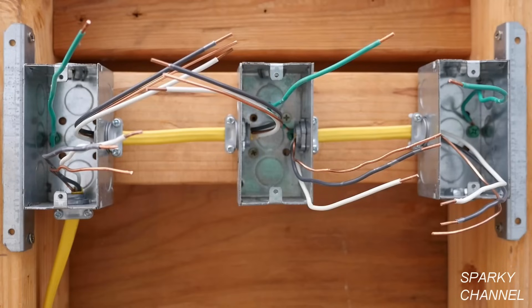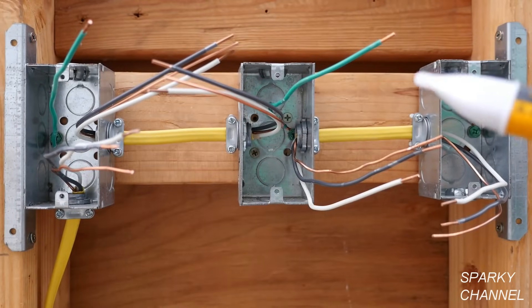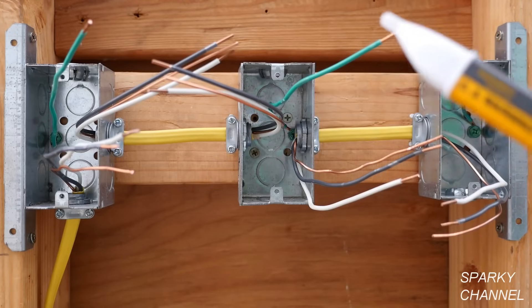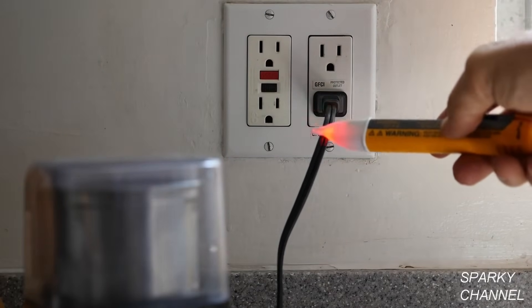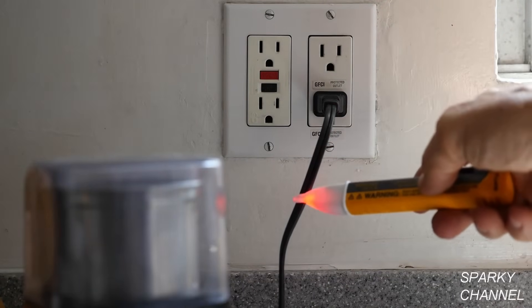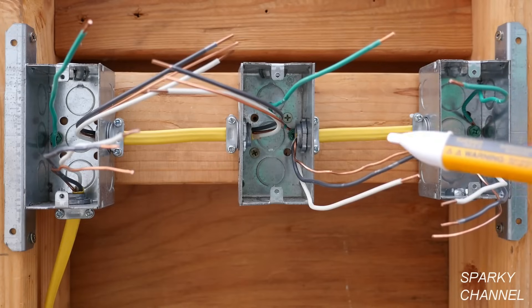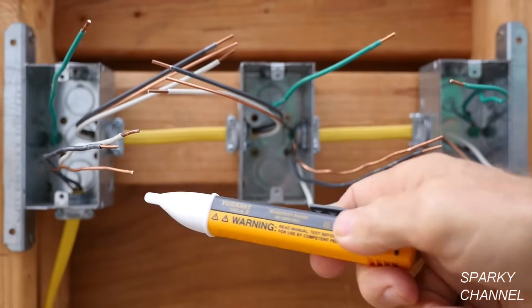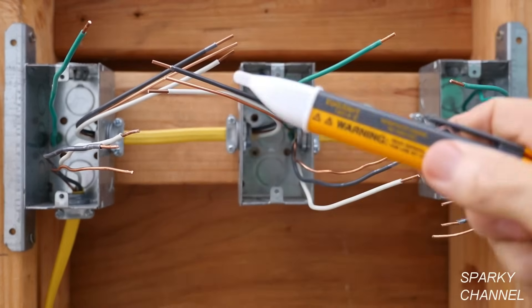The way I do this is to turn off the circuit breaker, remove all the receptacles from the circuit, and disconnect all the wires. I have turned off the circuit breaker, but the first thing I'm going to do is check for any live electricity in any of these boxes. Take your voltage detector, test it on a live known circuit to make sure it works properly, then use it on the wires in the boxes and check that none of them are live.